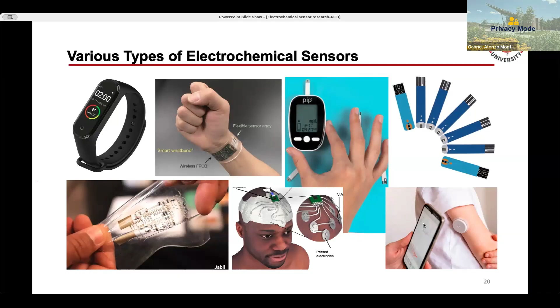So how did electrochemical sensing research start? It started in 1962. Clark and Lyons invented the first commercial blood glucose sensor. They modified the electrode with glucose oxidase enzyme, where we can oxidize the glucose into gluconic acid, and we get hydrogen peroxide. This hydrogen peroxide gets oxidized on the platinum surface, and we can measure the current, which can be amplified, and we can match it with the glucose concentration. That is how it started.